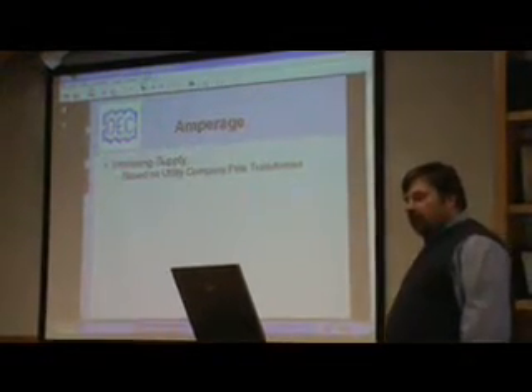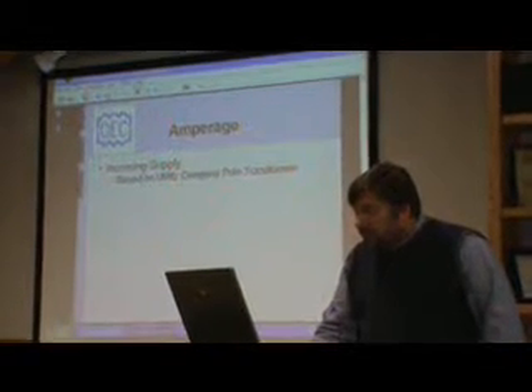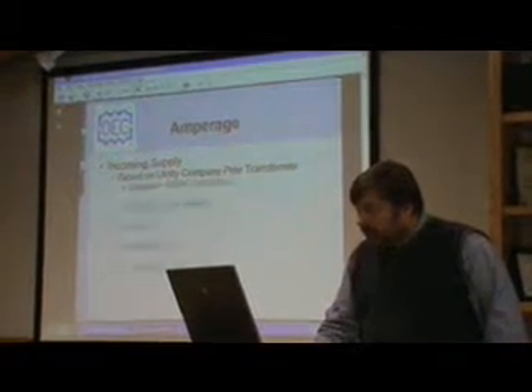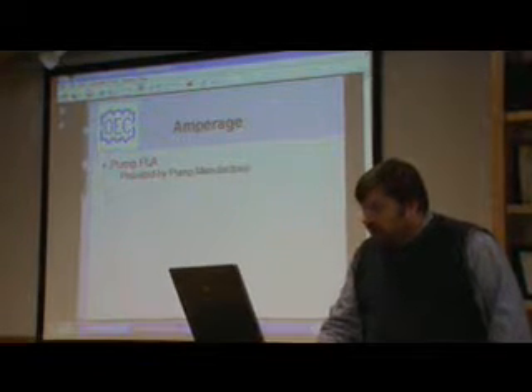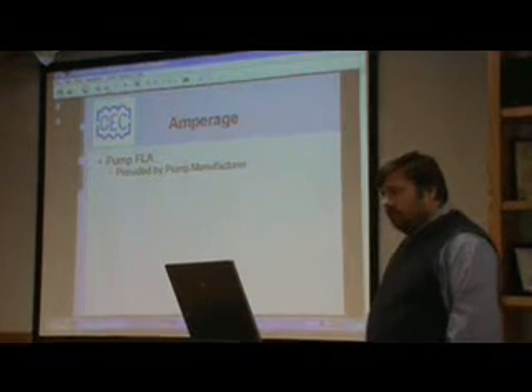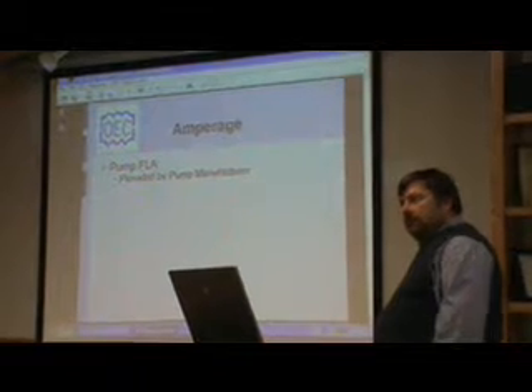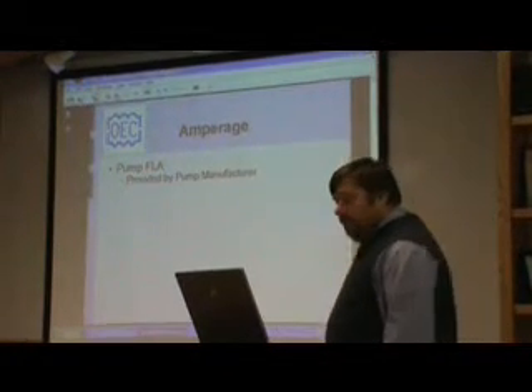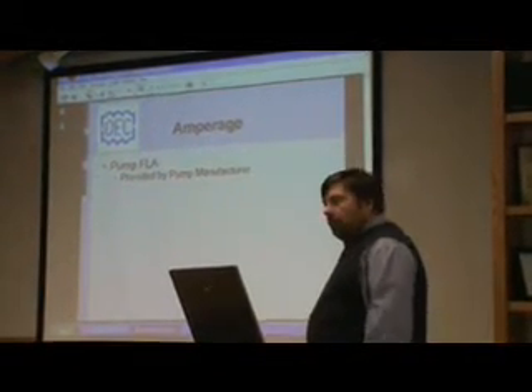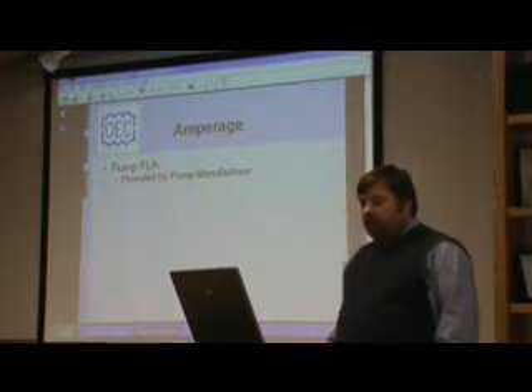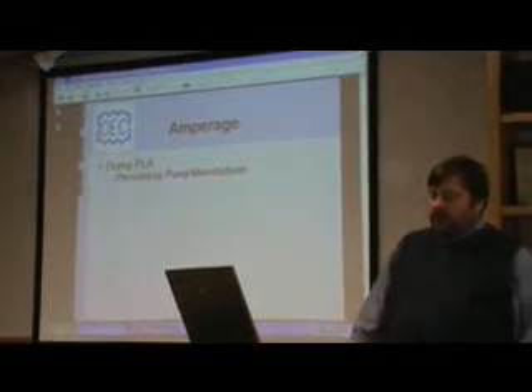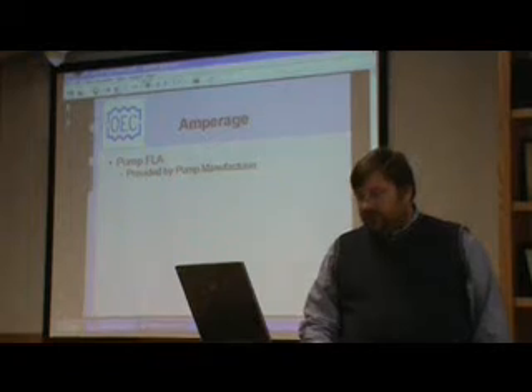The next thing that we like to talk about when we talk about control panels is amperage. I don't think this slide is in your packet. This is the incoming power supply stuff, so let's get it. I think your next page in your packet says pump full load amps, correct? And the pump full load amps is provided by the pump manufacturer. And we use that pump full load amps when we size the panels for a couple different things.